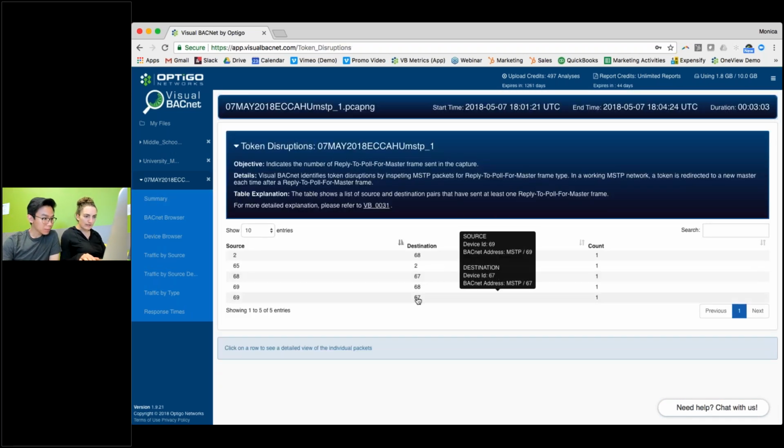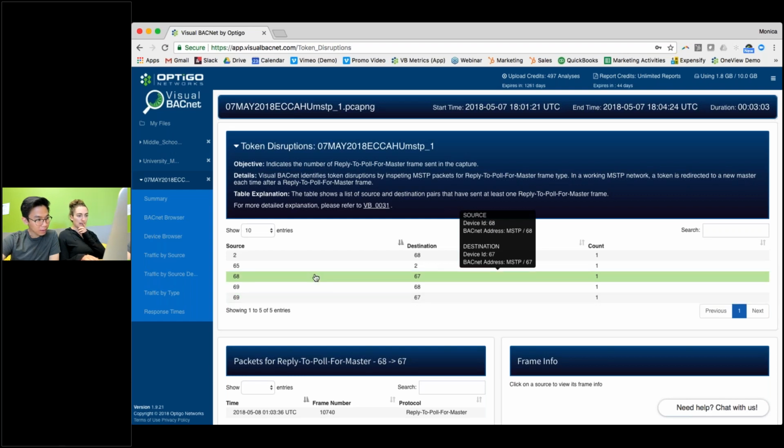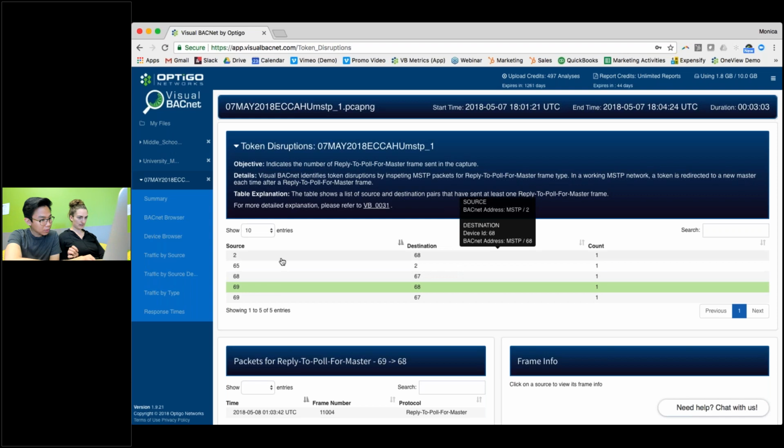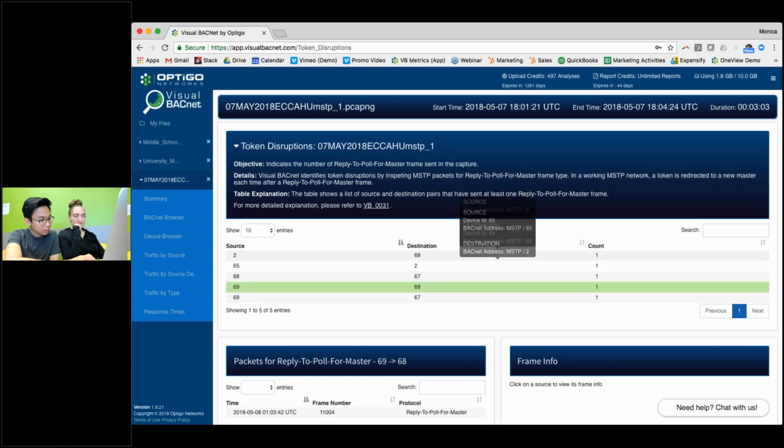So when 67 started talking to 69, 69 responded to 67 and said, I'm the master, because 68 is no longer online. That dropped out at 3:32, and then it came back online and said, I'm the master at 3:36. So yes, it's dropping out. And 69 is as well. Interestingly, 67, although it's doing the brunt of the work, is not going offline. 69 are though.